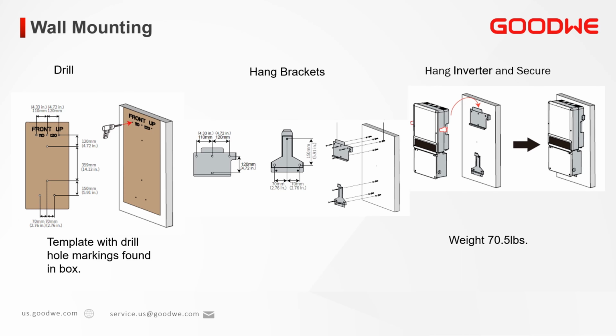Let's look at the selection of the wall for installation of the inverter. The AES is NEMA type 4X or IP66 rated, so it can be installed outside. Most of our installations are on an external wall near the utility meter. First, evaluate the selected site. Although the inverter doesn't have an external fan for cooling, the back of the inverter has heat sinks, which should have natural air ventilation, so make sure not to block the natural air around the inverter.